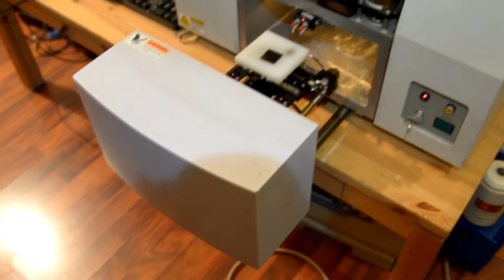Let's take a look at the chamber again. It's XYZ stage regulated. On the top there is a camera that gives you primary focus on the picture. When the focus is okay, then we know that we can start the X-ray measurement. The door has a seal for the vacuum, so if I want to evacuate the chamber, it's no problem.